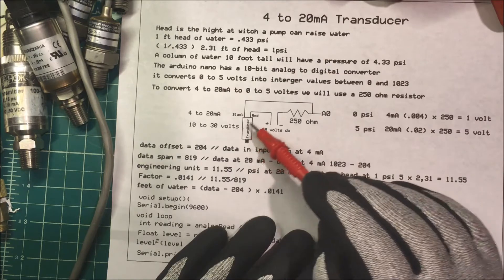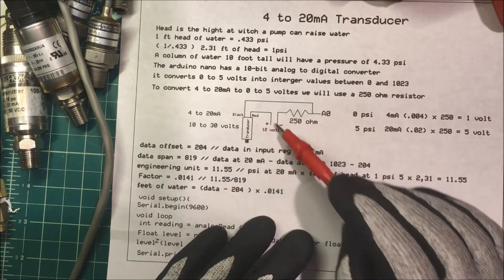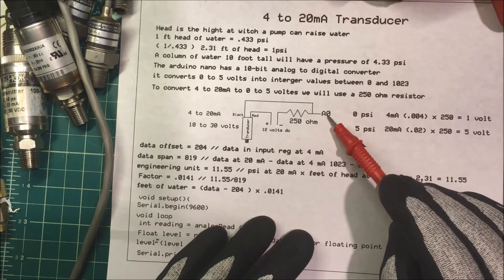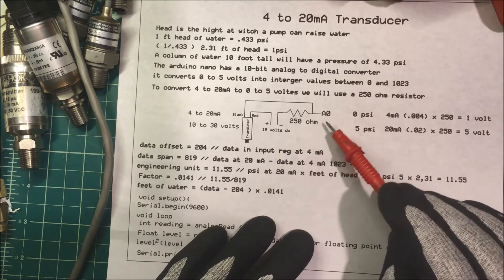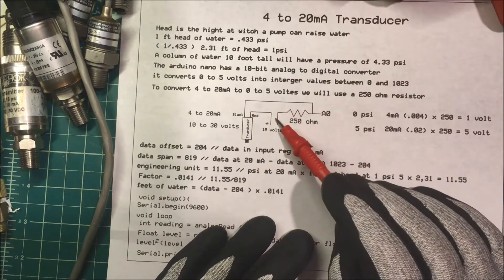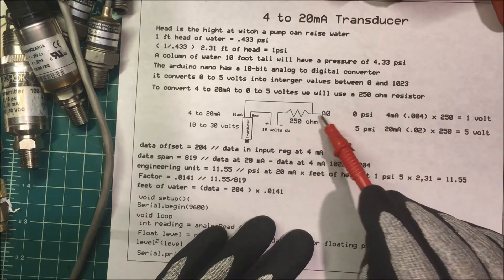Now we put the transducer in this loop here, it's just in series with the 250 ohm resistor, and then we have our analog input over here. Now if we run 4 milliamps through that loop, 4 times 250 ohms is going to be equal to 1 volt. We're going to drop 1 volt across here.